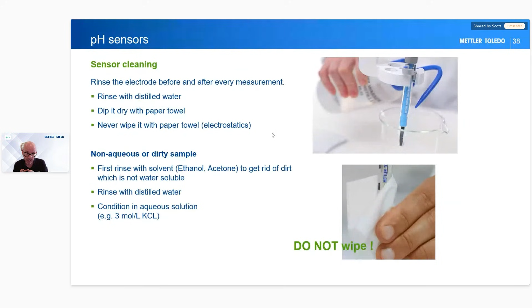If we're using something non-aqueous or dirty, we can wash with a solvent to get rid of dirt, but we must immediately wash with distilled water and get it back into some sort of conditioning solution, back into storage solution or whatever else, because we don't want that electrode to dry out. Again, if it dries out, that layer of gel shrinks and cracks, and we don't want that. So after we've done that, we've now got a clean electrode, we're ready to go.